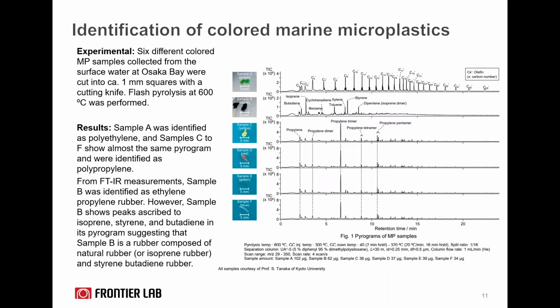Using the F-Search library version 3.6, sample A was identified as polyethylene. How we identified it was by seeing the fragmentation of polyethylene as it breaks down in a random scission manner, and F-Search identified every pyrolysate to its corresponding polymer. That's how F-Search allowed us to identify those specific pyrolysates as polyethylene for sample A. Then samples C to F showed almost the same pyrogram, as you can see here, and they were identified as polypropylene. They were pretty simple samples because it was just one polymer.